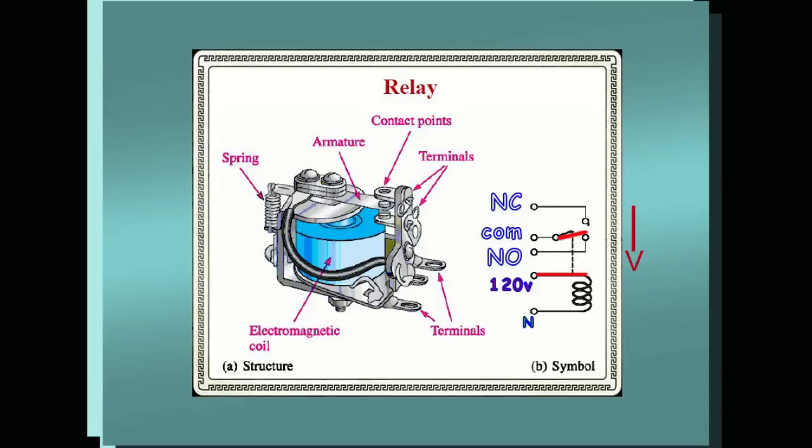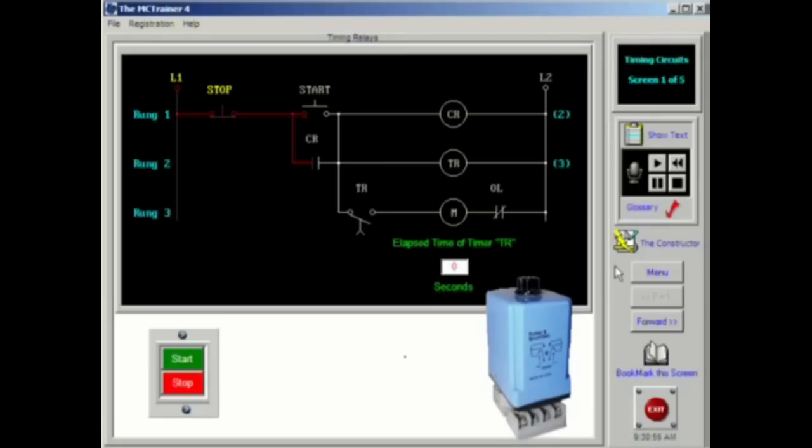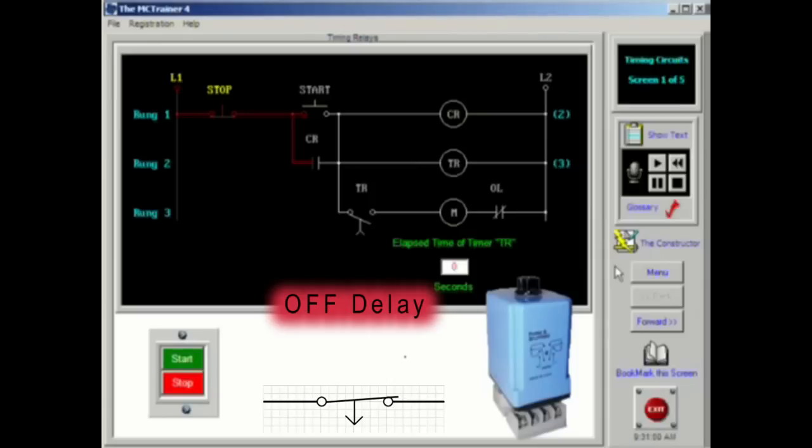Opening the initiating switch will begin the timing sequence. After the time lag, the contacts will return to their normal state. Off delay relays will have normally closed, timed closed, and normally open, timed open contacts.